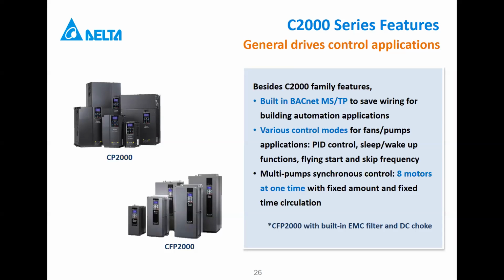And if you remember my M300 series webinar, you realize that for the fan and pump industry, normally you do not only use one pump in a large application. You might have many pumps, and we actually have multi-pump synchronous control for our CP and CFP 2000 series. So you can control up to 8 motors or 8 pumps at one time, either with a fixed amount based on constant pressure mode, or you can do a fixed time circulation where you vary the duration each motor runs for your application, up to 8 motors at one time.